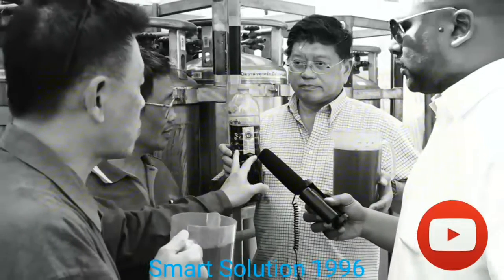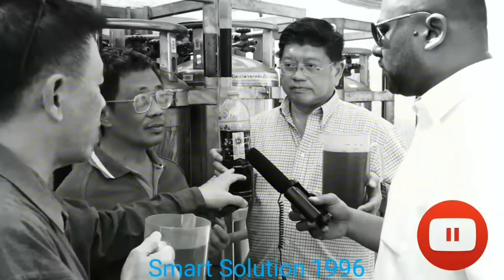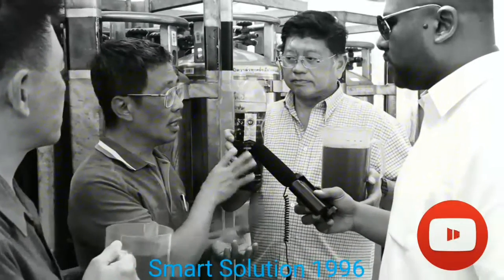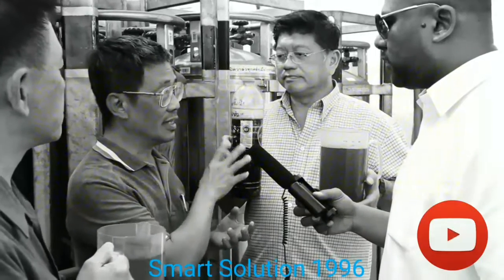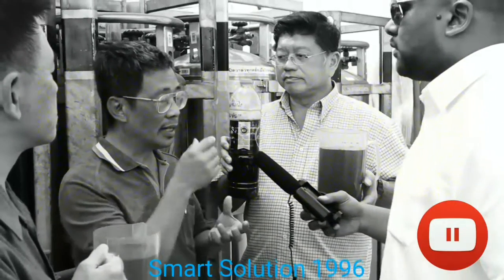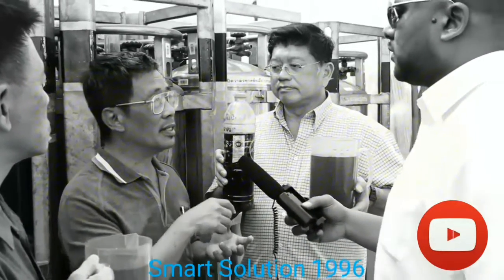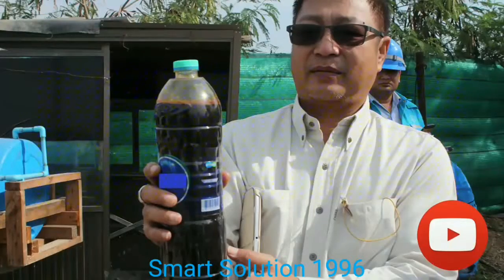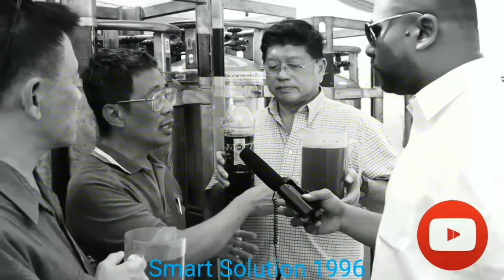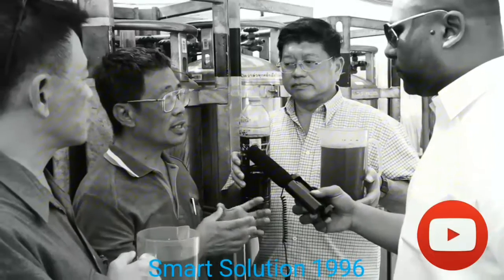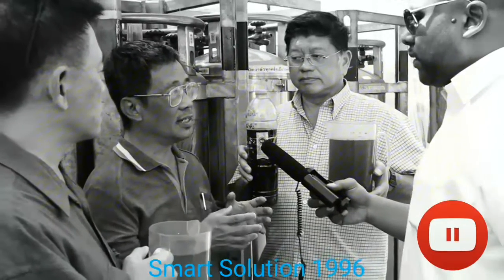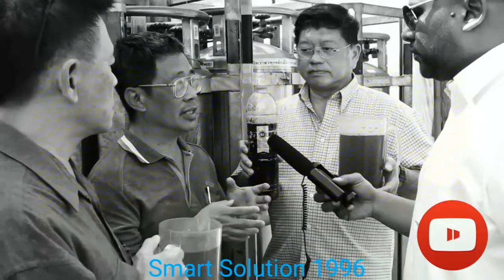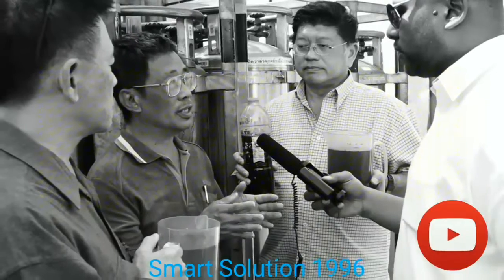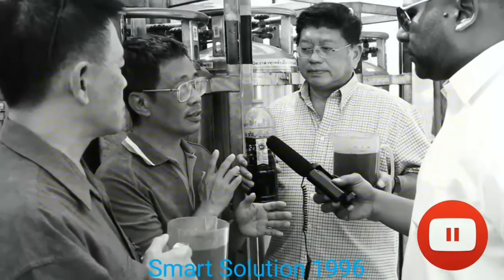Can you tell me the details of this waste? The dissolved solids here are so high that a standard TDS meter cannot measure them, more than 10,000. The reason we dilute is that the higher the TDS, the better the conductivity, so the machine would consume a lot of current.